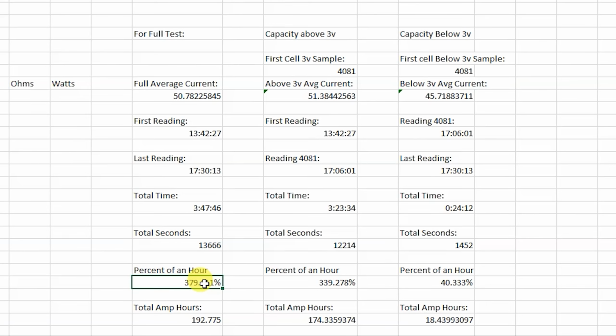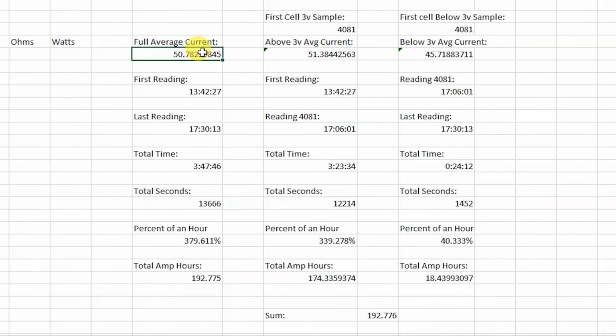We take that percentage multiplied by the average current, and that gives us the amp hours. For the whole test, I got 192.775 amp hours. Keep in mind, these batteries are only rated for 180 amp hours, so in this test it went far over that 180 amp hour figure, which is why I personally like these Calb cells, simply because they go way beyond their spec.